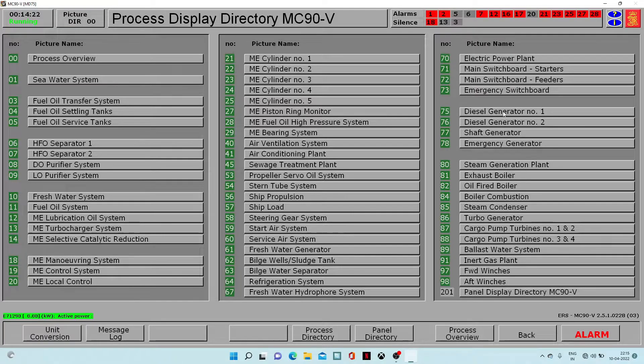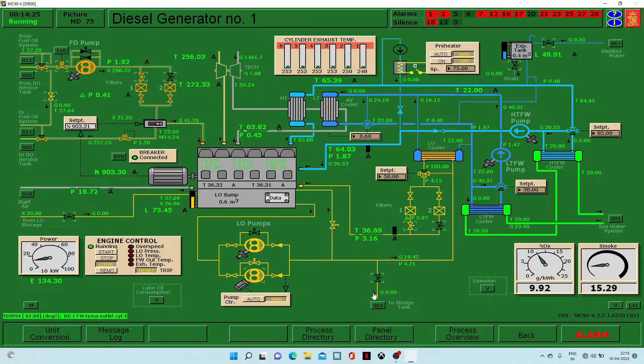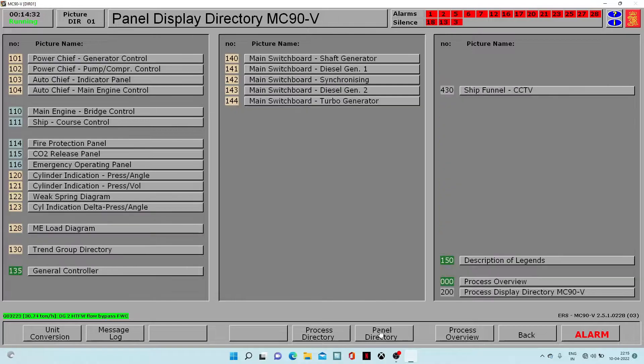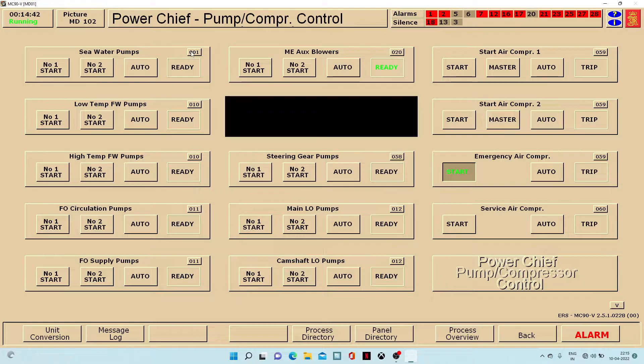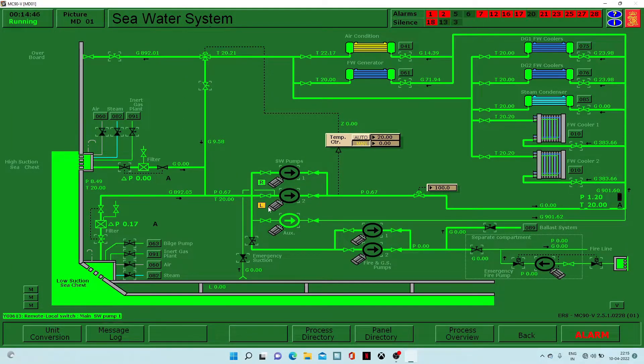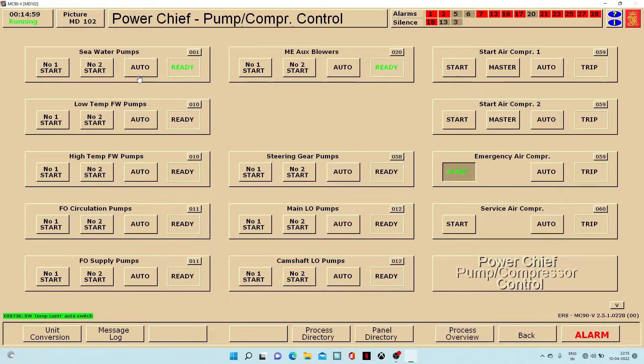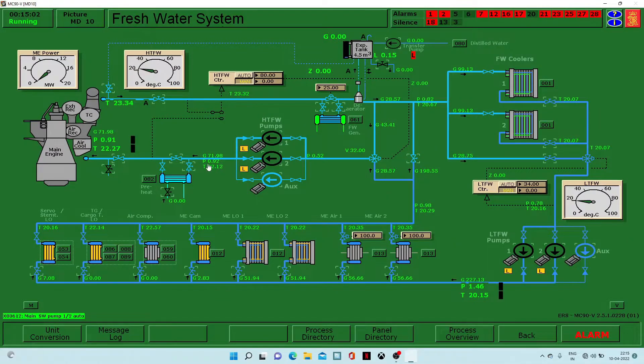Now we can go to the process directory and monitor — diesel generator one is running, diesel generator two is running fine. Our work is almost complete. Now we go to the panel directory, then power 102 — chief pump compressor control. We click on 001 and put it into remote mode: click on L and it will change to R, where R means remote and L means local. Then we put it on auto. We come back and the same process for the next one — click L to change to R, then set to auto.